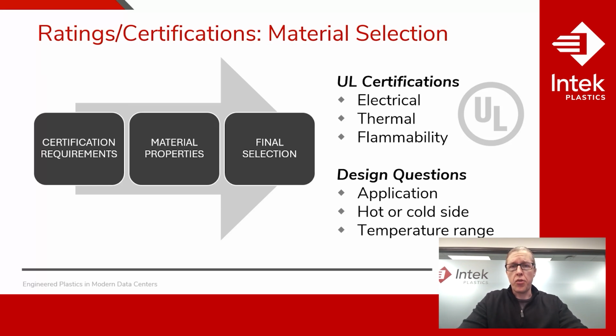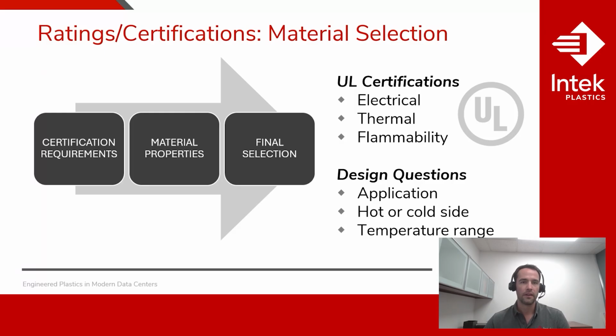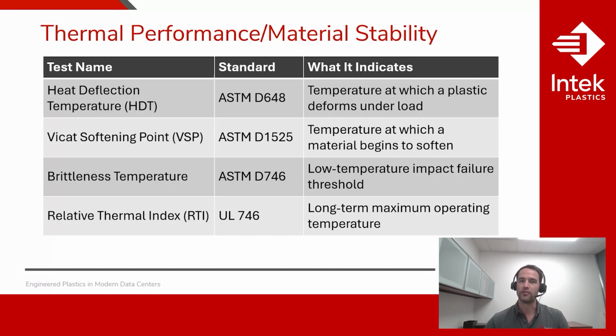Up next is thermal performance and material stability. Levi, would you chime in on this part of the design process? Yeah, absolutely. Understanding the temperature range of a plastic material, or the environment it's going to be exposed to, is critical to ensuring it meets performance requirements in a data center environment. All plastics respond to temperature changes to varying degrees. At elevated temperatures they can soften and deform, and at low temperatures they can become brittle and might fracture. Selecting a material that maintains its key properties across the full operating range is essential.